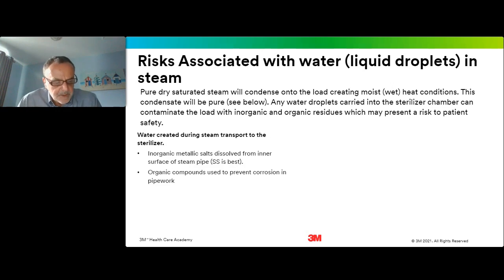So if condensation takes place in the pipework as the steam is transported to the steriliser chamber, then inorganic metallic salts can be dissolved in the condensate, unless of course you're using stainless steel for your pipework, which modern installations would tend to use, but the older installations are probably using standard iron pipework to transport the steam around the hospital. Similarly, the engineering community might be adding things to the boiler and the steam pipework to prevent corrosion in the form of filming amines or anti-corrosion compounds into the boiler feed water.